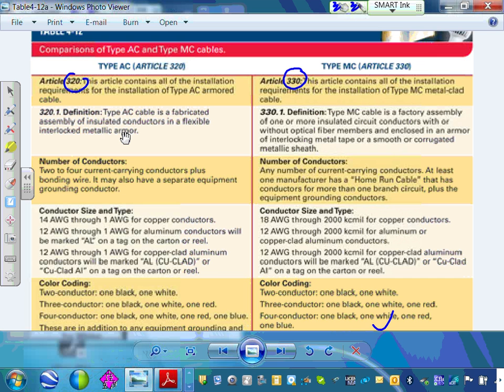I can't emphasize this enough as we move through, because I assume many of you have never walked through a wiring article. When you see an article that talks about wiring, can I get you to understand - when they have article 320, the first .1 is always what? Always the definition. We have close to 60 wiring methods, and every time you have a wiring method article, .1 always defines what it is. Does that make sense? So can I get you to understand point 1 is always the definition, defining what this is all about.